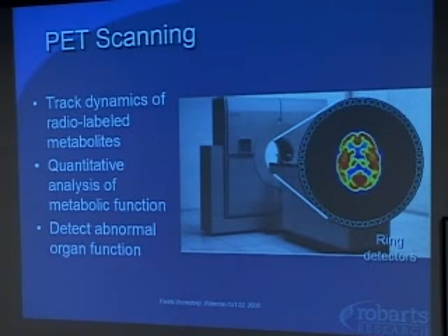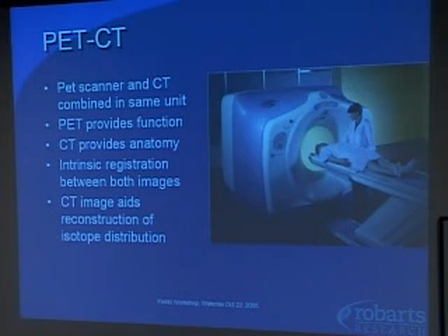Of course, these need to be interpreted in the context of the anatomy, and so up until recently, PET scans were almost always registered to MR or CT after the fact. Now it's becoming quite common. In fact, most PET scanners now, I think, are delivered with a built-in CT scanner, which means that the CT and PET are intrinsically registered. And so this not only provides the anatomy, it also, having the CT image registered to the PET data, helps tremendously in the accuracy of the reconstruction, because you can use the information in the CT scanner as part of the PET reconstruction algorithm.